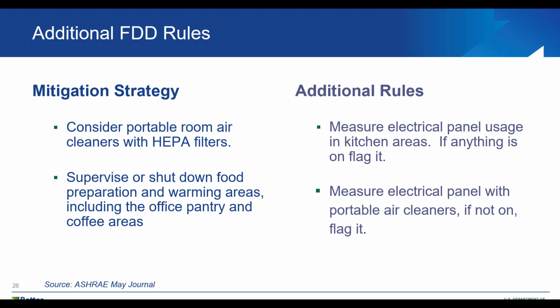I was in a school building and the cafeteria had a cleaner in there, but this was the day that they didn't have anyone in there. So there was no reason to be running the cleaner. So one of the things to do is you can add additional BAS points, connect to an electrical panel, for example. You could do this in the kitchen also if the kitchen has things left on, like the coffee makers, and to make sure that things are shut off when people aren't there. So this actually gives an opportunity to look at opportunities to reduce energy consumption through new faults that are created based on new equipment that's been installed.